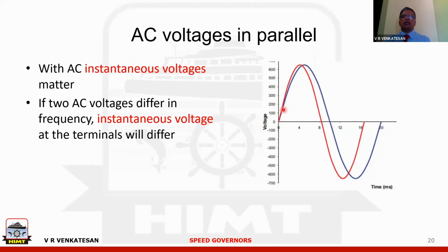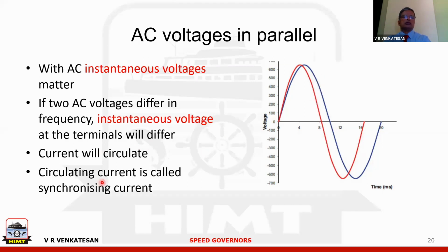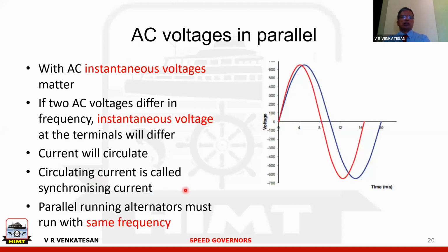So for example, if you see, the blue line is the waveform of one alternator, and the red line is the waveform of the other alternator, which is running in parallel. The difference between the two is their frequency is not same. If the frequency is not same, you will get difference in the voltage. In these conditions, current will circulate. The circulating current is called synchronizing current, and the synchronizing current will not allow the alternators to run at two different frequencies.